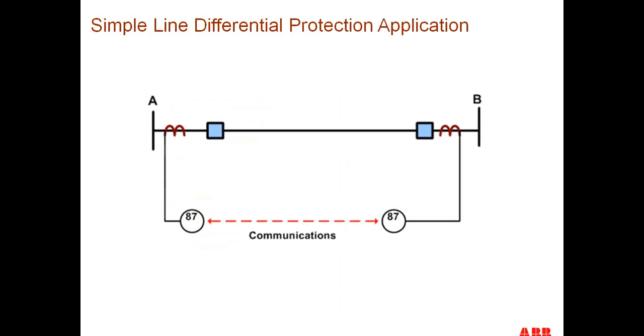Starting off with what a line differential protection application is. Here we see a single line diagram of a transmission line with breakers at either end between buses A and B. We see CTs located at each end of the line on the bus end of the breakers, feeding into an 87 type relay.